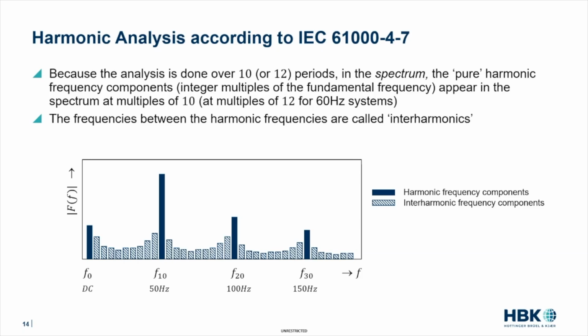So you have a large number of frequency components, but only every 10th is a multiple of your nominal frequency. So you have 50 Hertz and 100 Hertz, but you also have 55 Hertz and 60 Hertz, etc. And what the standard says is that what I call the pure harmonic frequencies are called by the standard harmonic frequency components. So they are dark blue in this slide. And all the frequency components between them are called interharmonic frequency components.